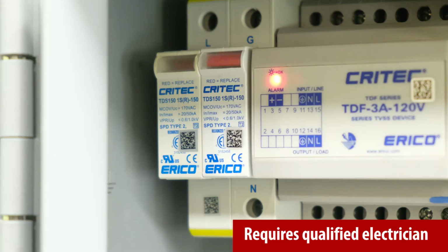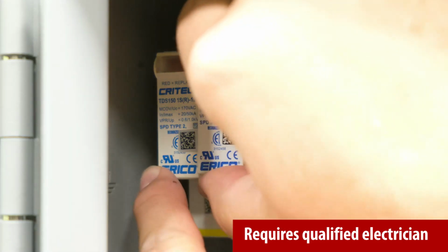Another component that could cause an outage is a faulted surge protection device. With newer systems, surge protection devices, sometimes referred to as SPDs, are integrated into the system due to the sensitivity of the electronics of LED drivers and such. These SPDs can often be located remotely in a cabinet 8 to 10 feet off the ground. Depending on the manufacturer, they may be located in the fixture at the top of the pole. During your inspection process, you want to visually inspect these SPDs to see if they have faulted.